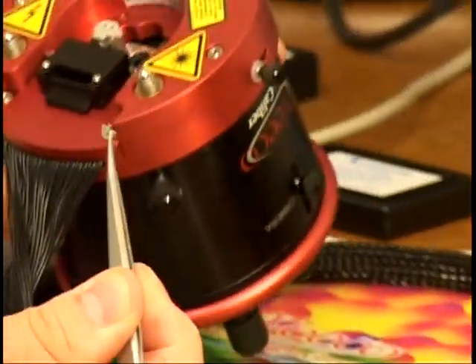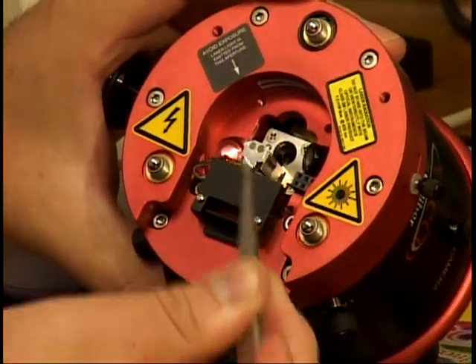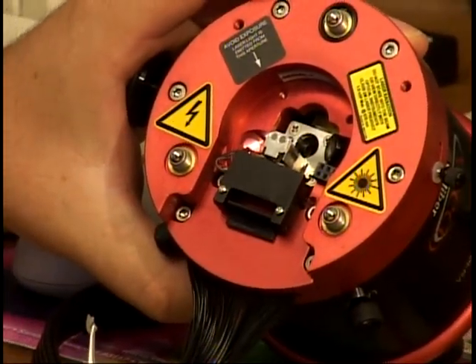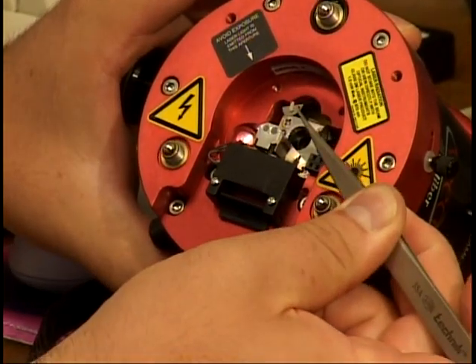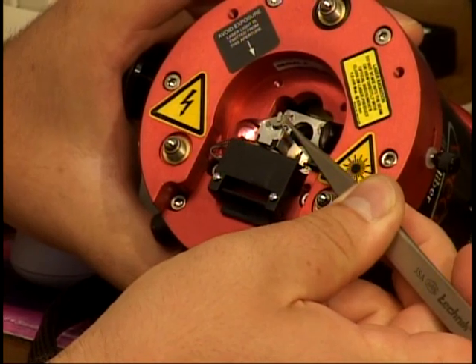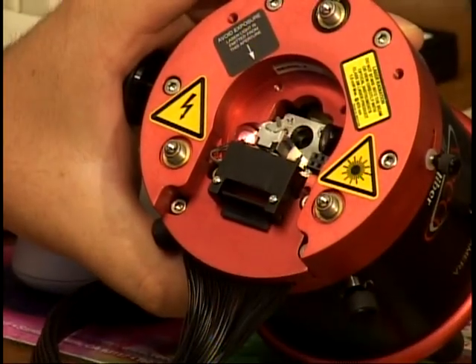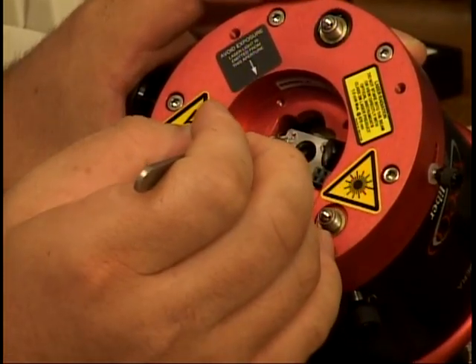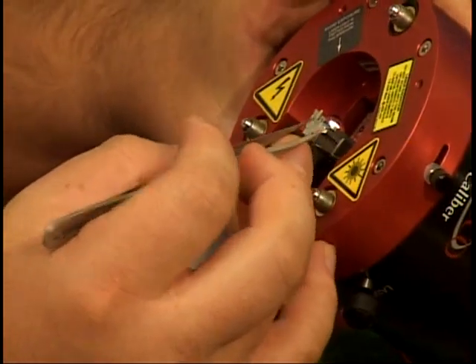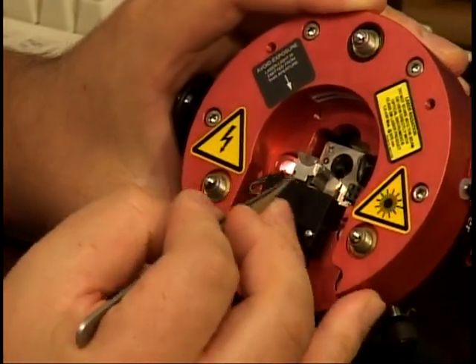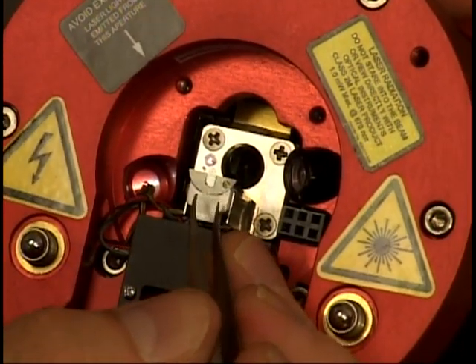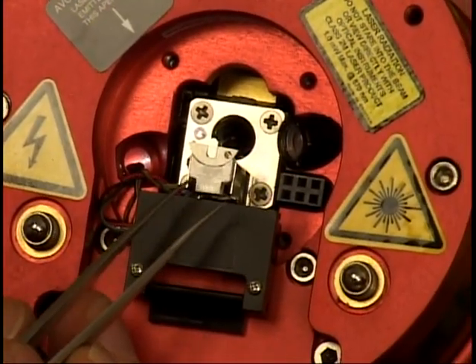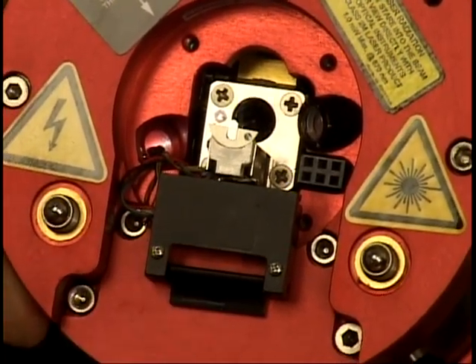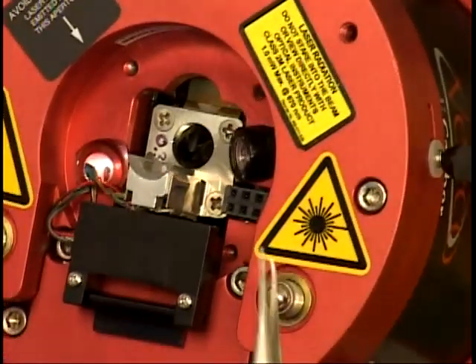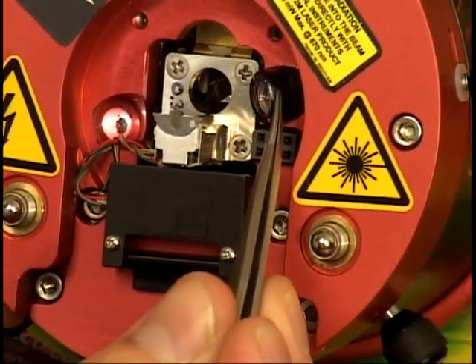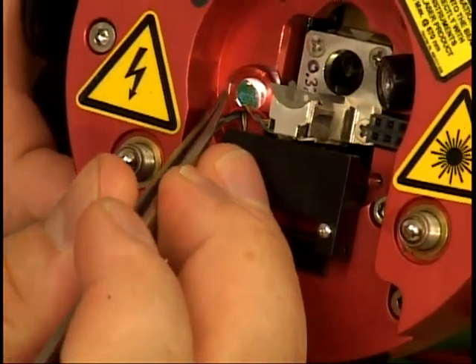With the probe in hand, with the tweezers, you have your Z scanner. In the Z scanner, there's two magnets that will hold your probe in place. Actually, put it pretty close to alignment. So you just bring it up closer and just let it grab on. Use your tweezers to adjust it to where it's perfectly straight, and at least parallel to the back of it. But don't push hard on this because this cap is very, very sensitive. It's easily broken if you push on it too hard. See, I can show it right here. This is actually your camera. To the right, directly opposite is your light.